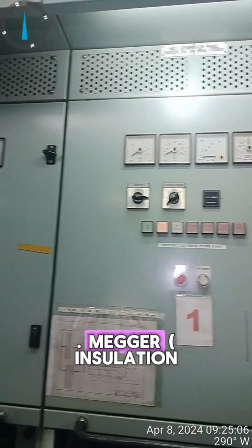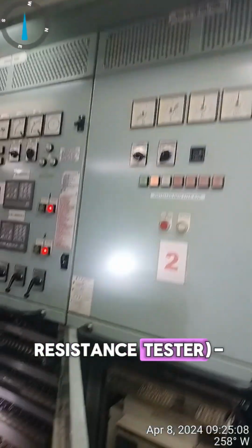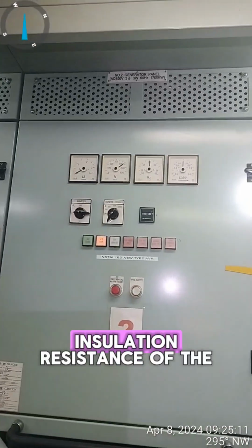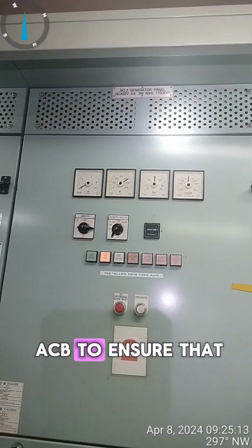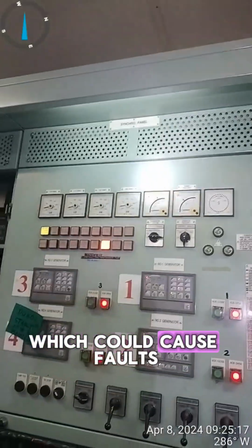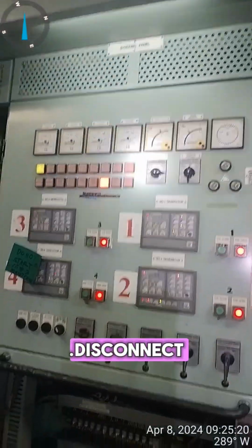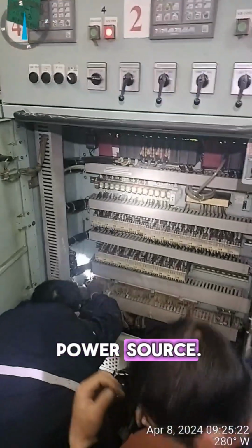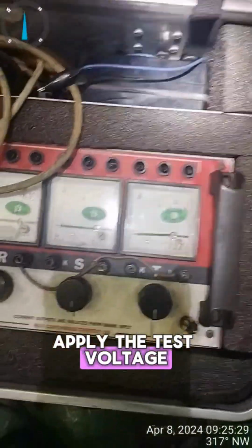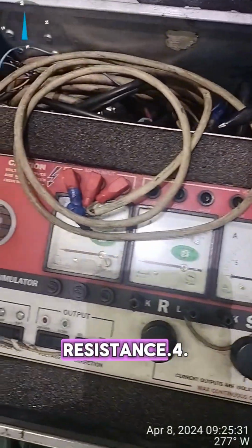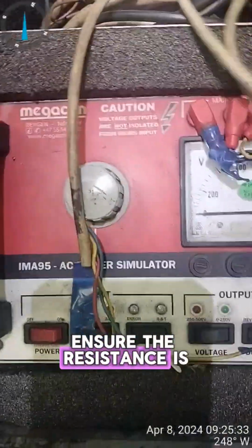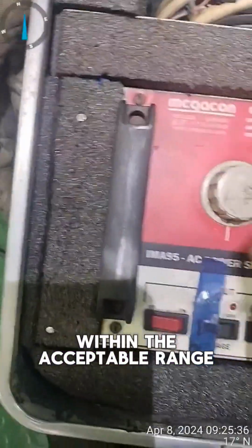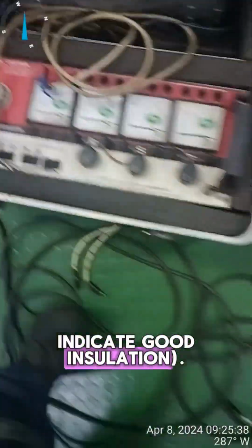3. Megger insulation resistance tester. Function: measures the insulation resistance of the ACB to ensure that there are no leaks of current across the insulation, which could cause faults. Steps: 1. Disconnect the ACB from the power source. 2. Connect the Megger leads to the ACB terminals. 3. Apply the test voltage and measure insulation resistance. 4. Ensure the resistance is within the acceptable range. High resistance values indicate good insulation.